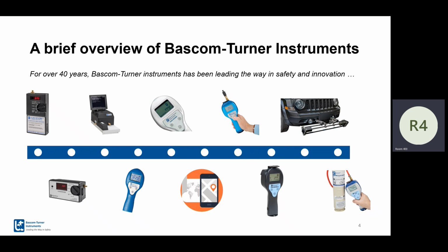The very first company in the downstream space to offer integrated Bluetooth and GPS in our units. So that's been something we've been doing for about 15 plus years now. One of the very first to offer on-unit methane confirmation and detection, so we can detect as little as 50 parts per million volume, 1 liter sample of gas on our units in the field. Again, something really valuable for our downstream customers who need to determine, is it swamp gas or is it their gas?